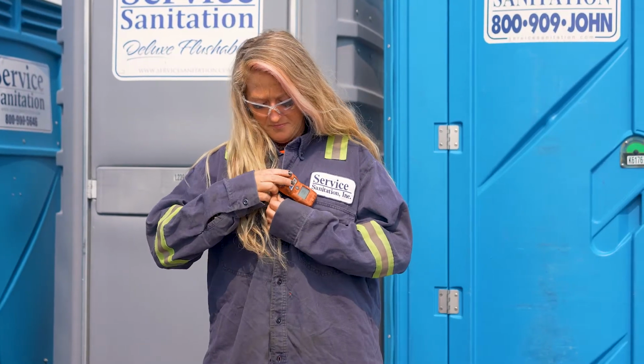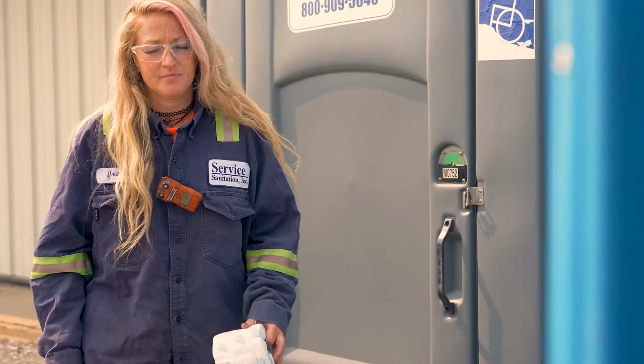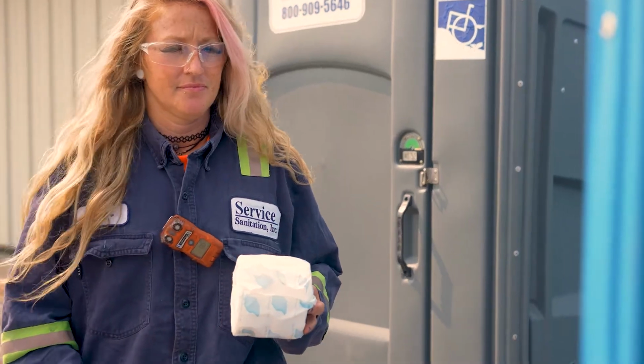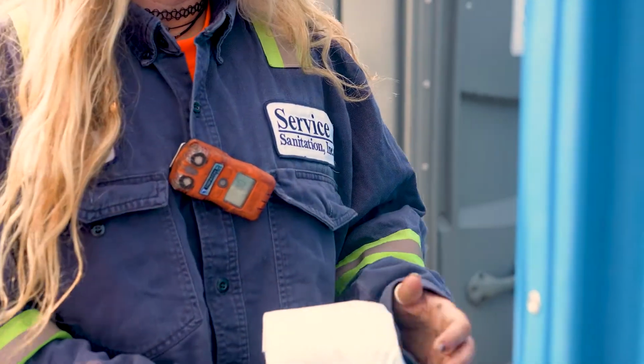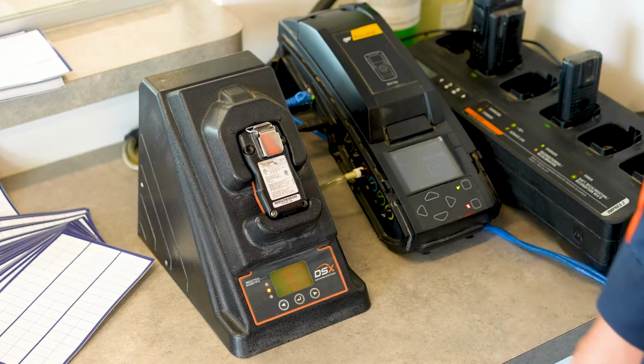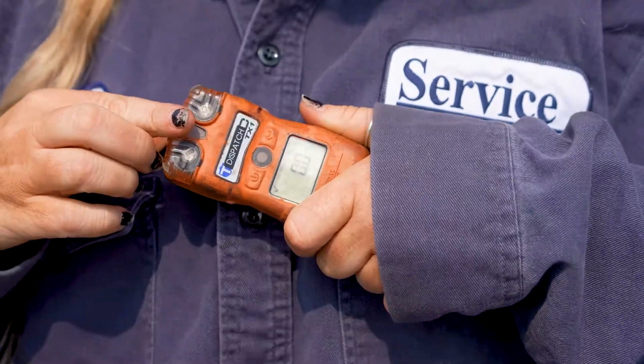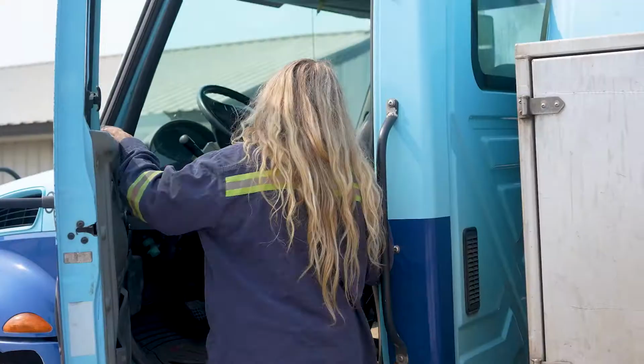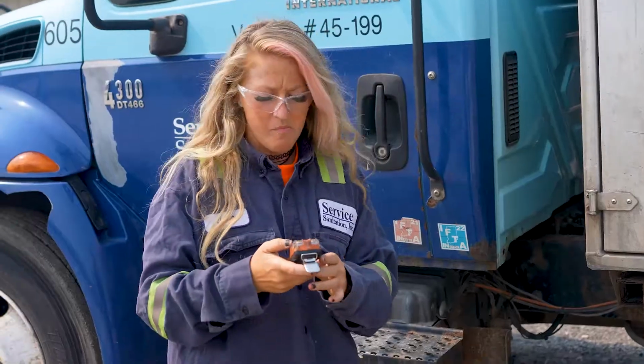The good news is that exposures to hydrogen sulfide are often easily preventable by way of wearing a personal monitoring device. When working inside a refinery such as BP, personal H2S monitors are required and must be powered up, bump tested, and attached to your shirt within 4 to 6 inches from your mouth and nose. This is where it will be most effective. Failure to do so can expose you to a possible exposure and/or the removal of your badge and credentials to access the plant.